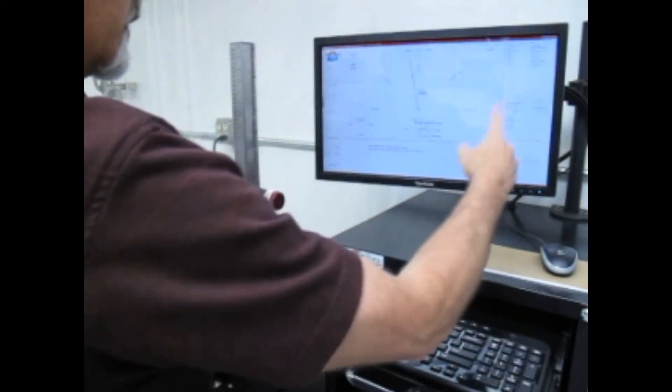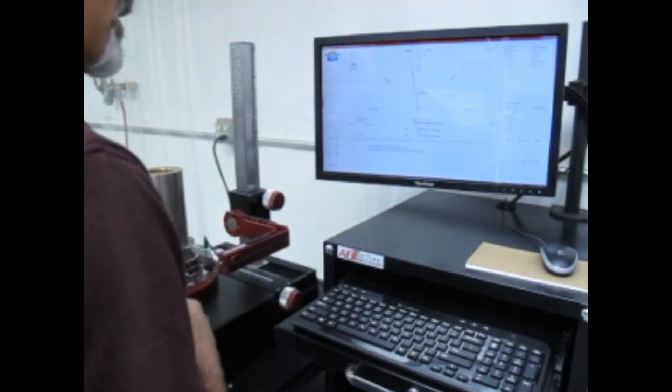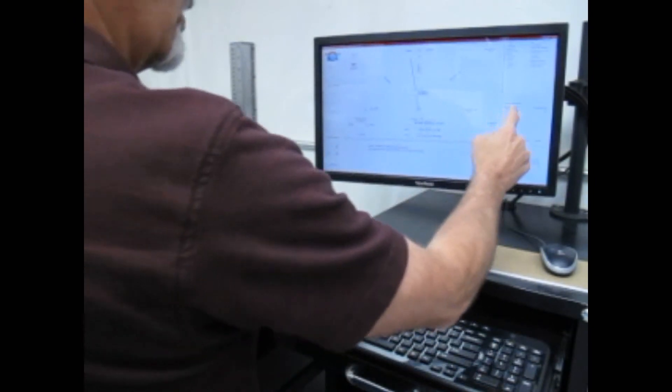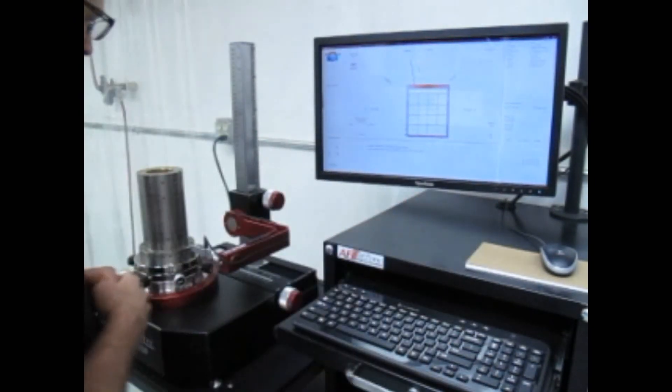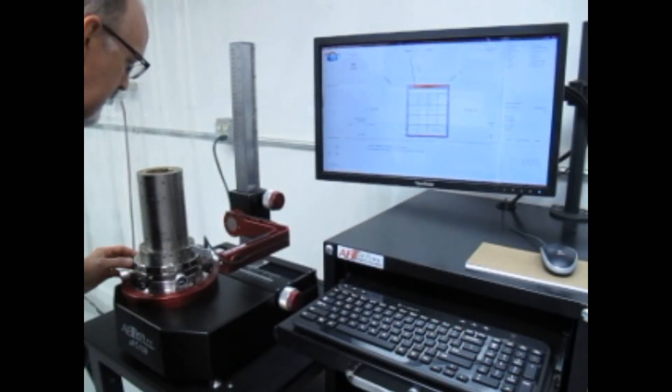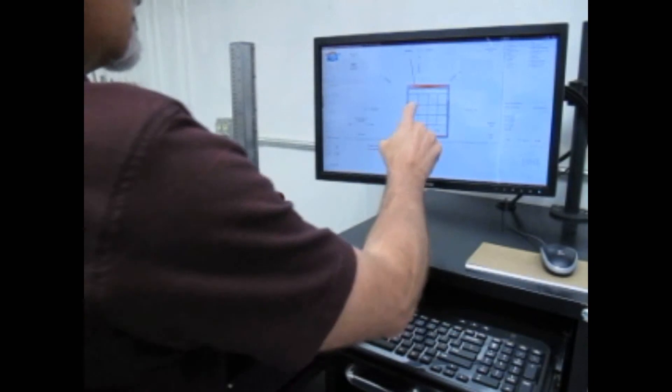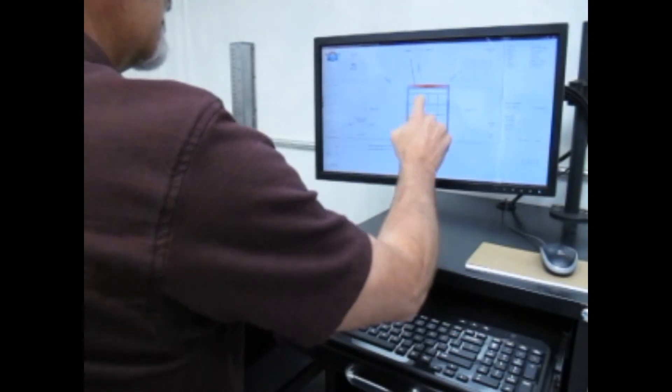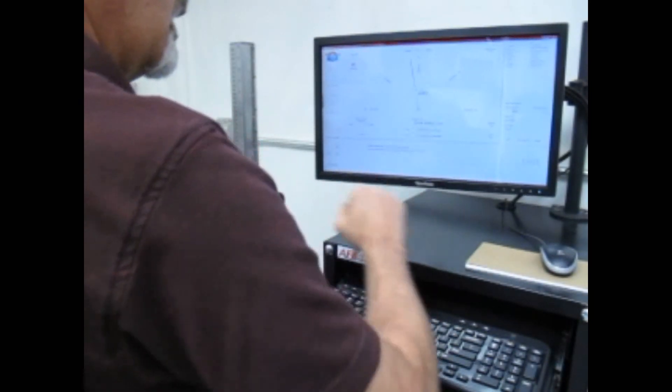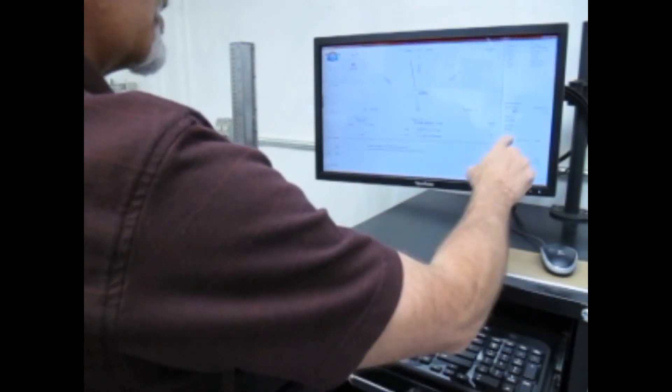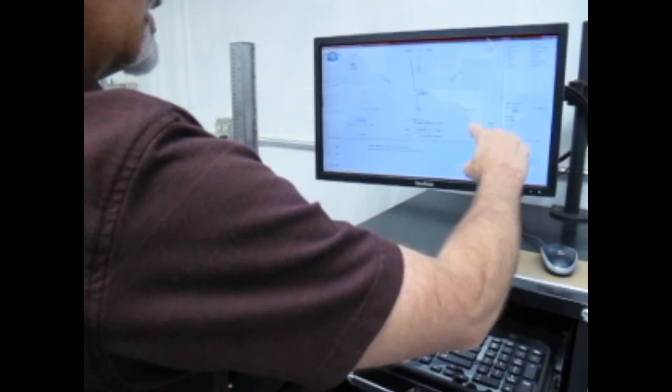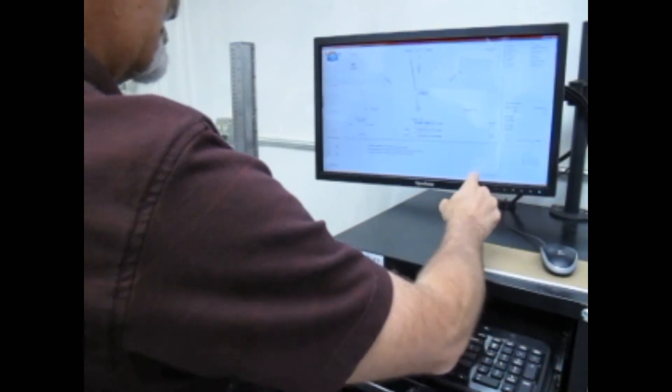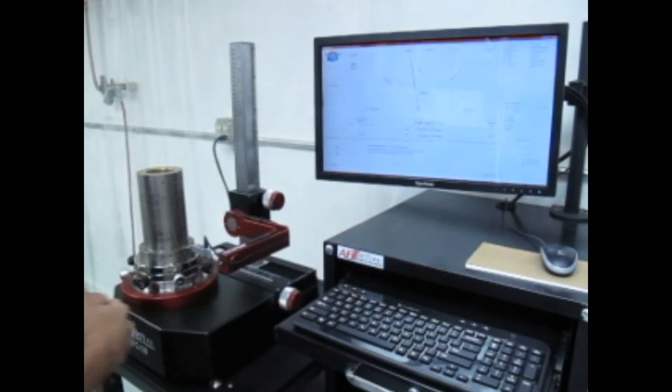And I have to input the information here as to the radius again. So I changed the radius. And now I'm at 1.875. And I'm still on a top face. And so I'm going to apply that and use the motor to take my measurement.